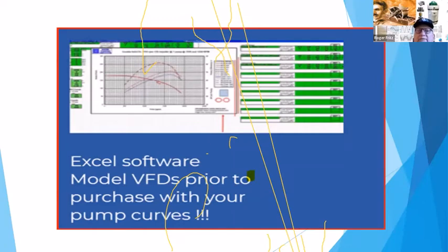So you bring the first acceleration up to, let's say, 30 hertz, where it starts pumping water quickly, normally within 2, 3, 4 seconds. And then you can set the second stage acceleration out to a longer period of time, when the thrust bearing's loaded properly and you're going on up in speed, so you don't want to create water hammer in the hydraulic circuit. So you're able to slowly bring that up to the next stage, maybe 30 seconds acceleration on the second, to eliminate that water hammer.